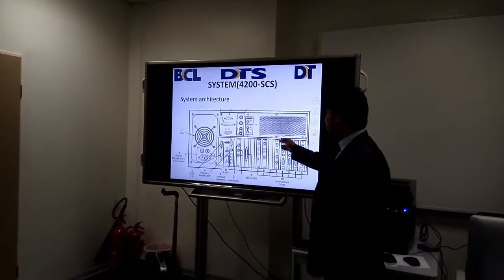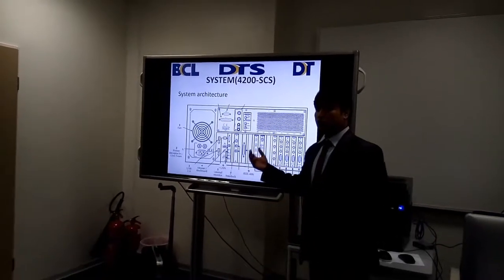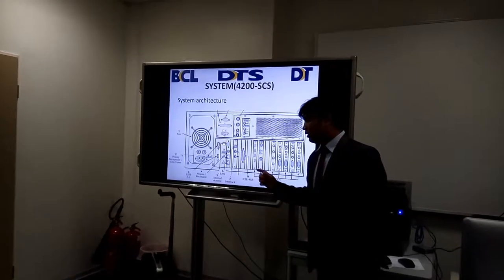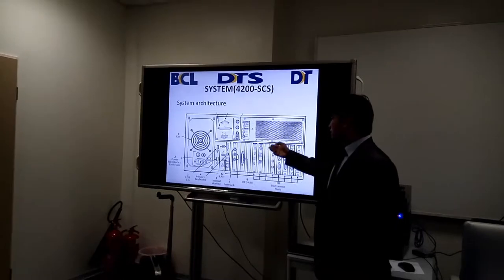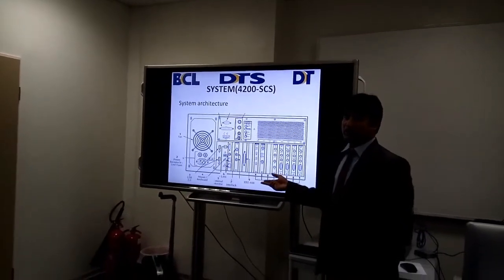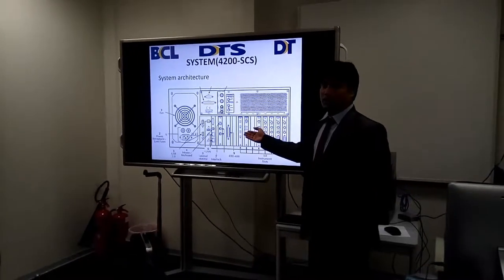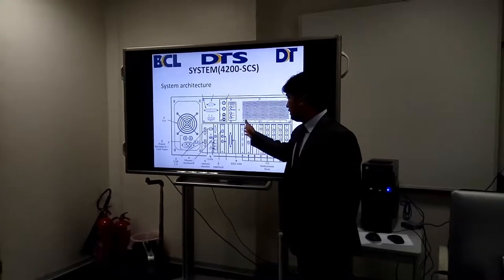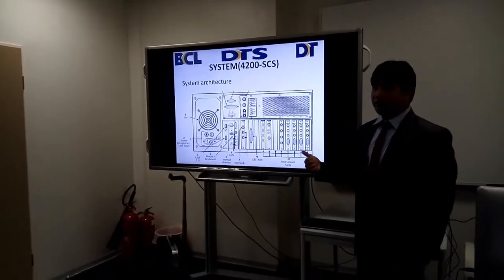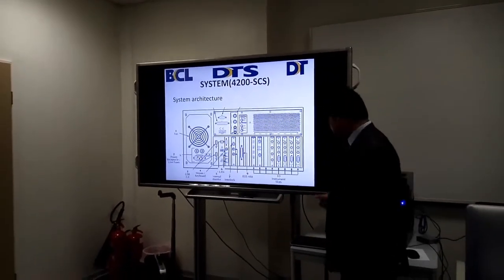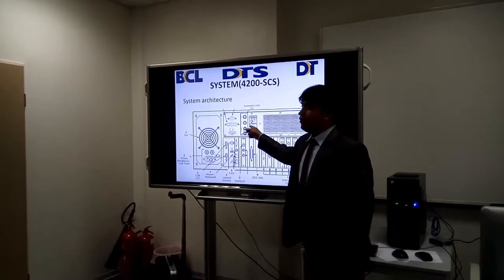The last point — this part is called the SMU part. SMU means source measurement unit. This source measurement unit is responsible: either you can source the current or you can source the voltage. All electrical devices depend on either voltage or current. Suppose you want to give some voltage to your device — by help of this source measurement unit, you can apply the voltage and measure the current. You can apply the current and measure the voltage, and you can do both together. It depends on your application. Here we have four SMUs, source measurement units. The next point is called the CV unit, which is installed in between, and we also use this CV unit for characterization of capacitive measurements. They are also giving one external ground common connection, and we have to understand how to use the sense line and everything.